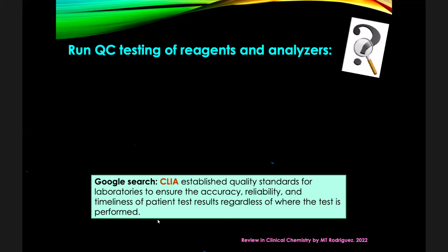Anong sabi niya? For routine test, sinabi ko na sa iyo ang routine test, at least 20 test requests in 24 hours to be considered routine. Ano nakalagay dito, children? For routine test, run control test at least once every 24 hours. It means before you process all the patient samples in clinical chemistry section, you should test the machine, the reagent, the procedure, challenge it against the control samples. Normal and the abnormal. Do not forget that, people. Huwag kalilimutan, at least 24 hours.